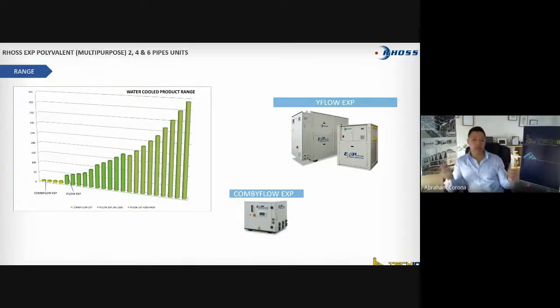For the minimum recommended volume, you can go to our manuals for more detail, but please consider as a general rule 10 liters per kilowatt. That gives you a good safe area to work with. This is the kind of information we can help you build. For example, when we talked about 6-pipe, look at this baby unit here. You see 6-pipe connections there, but that's not a 6-pipe unit. It is basically a 4-pipe unit, cooling and heating, and the other one is condenser water. That is going to be classed as a water-cooled unit.